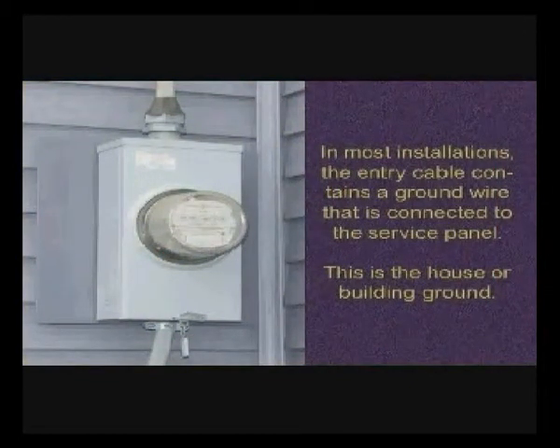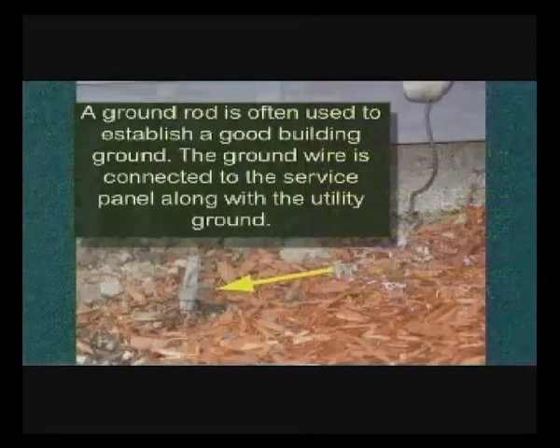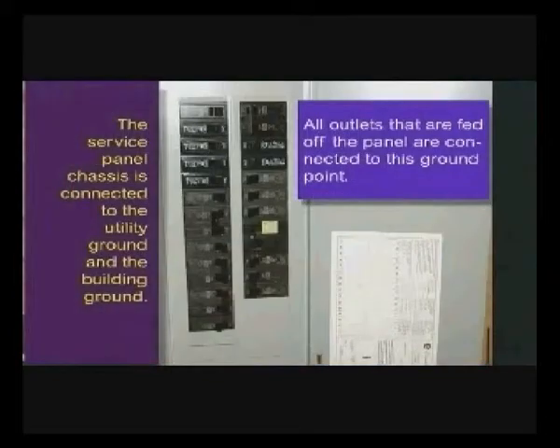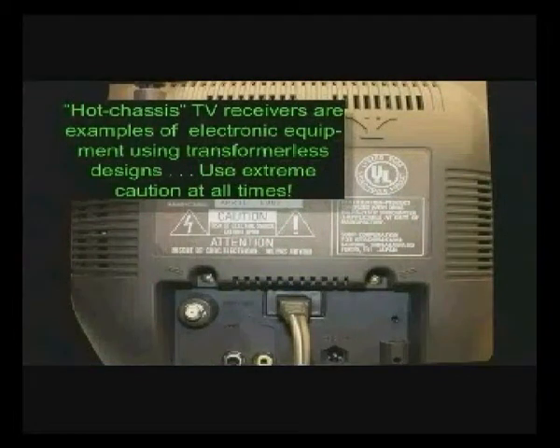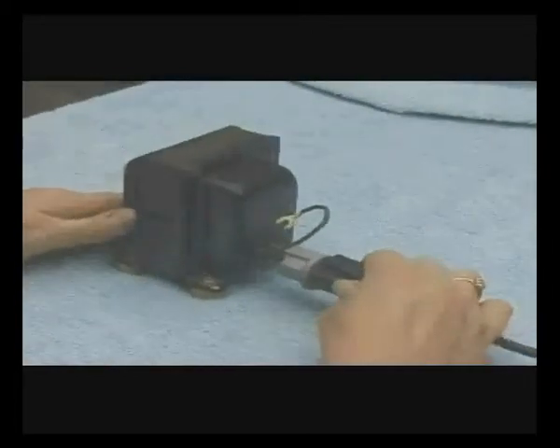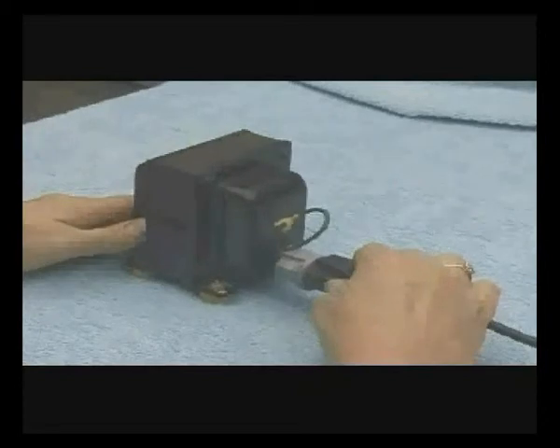In most installations, the entry cable contains a ground wire connected to the service panel — this is the actual building ground. A ground rod is often used to establish a good ground. The service panel chassis is connected to the utility ground and the building ground, and all outlets are fed off the panel and thereby connected to this ground point. Hot chassis TV receivers are examples of electronic equipment using transformerless designs. Use extreme caution at all times and preferably an isolation transformer. Note there is no ground connection in this case, and it is acceptable to use a cheater plug since the float is provided by the transformer.